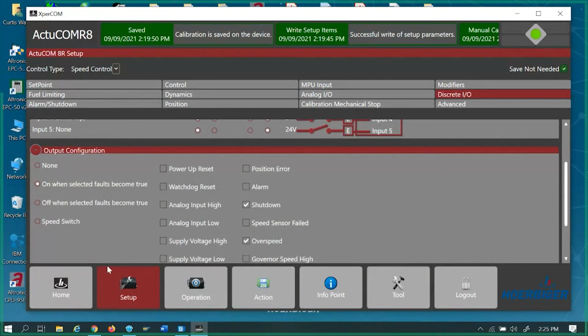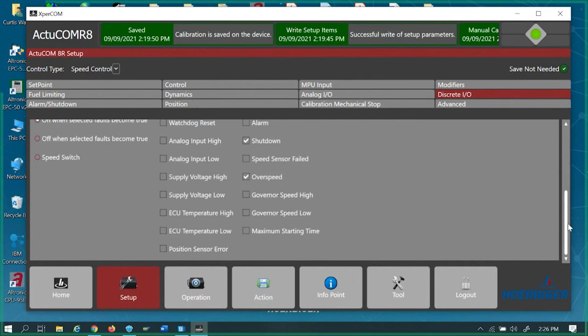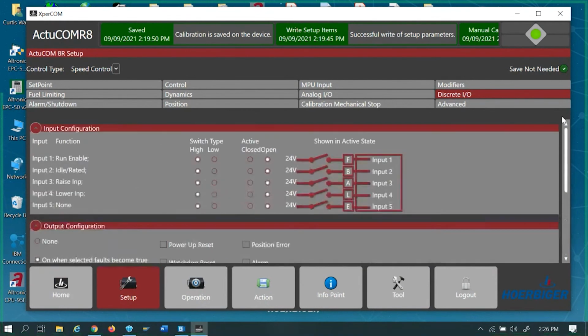Output configuration, I can do an output on certain shutdowns. If, say, I'm sending it a 4 to 20, I can say I want to flag it if I got too much milliamps on it. So if I go to 25 milliamps, it's going to flag it, shut you down, and go from there. So typically I don't use the shutdowns off of this. If you need to, they're there to use if you needed them.